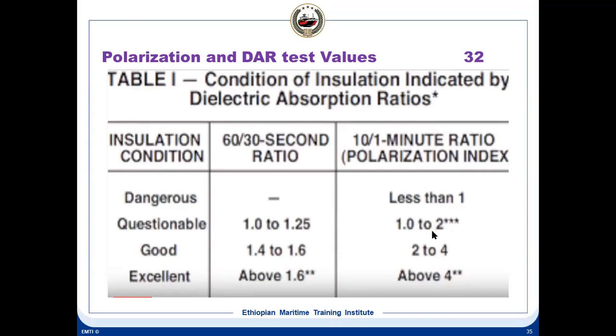It cannot be used. So as I told you, this is done when the generator is lying idle for a long time, or in the refit time, or when some major repair has been done on the winding. Suppose the winding is burnt or cracked and you rewind it, then you have to go for this polarization index test and check these values. If it is above 4, it is excellent. 2 to 4 is also good, but less than 2 is questionable condition.